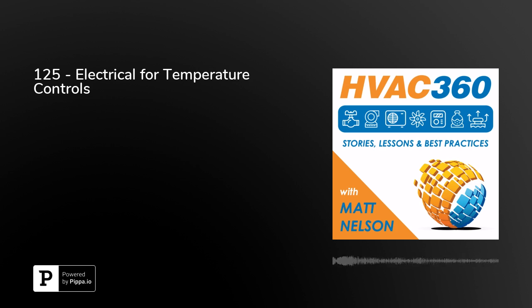The one nice thing about the 4 to 20 milliamp is it doesn't really have the same problems with noise, because you're not using that voltage. You don't get that interference from motors, relays, and those noisy power supplies. Another bonus is that you have a positive zero position.